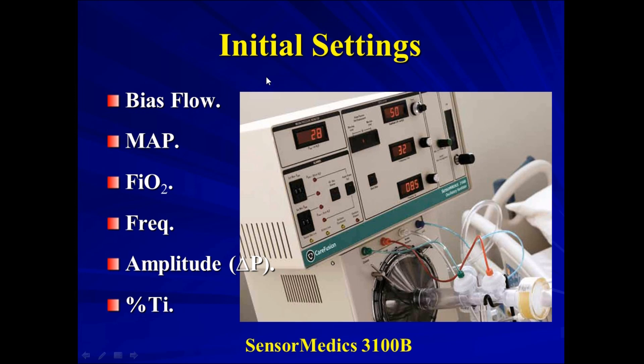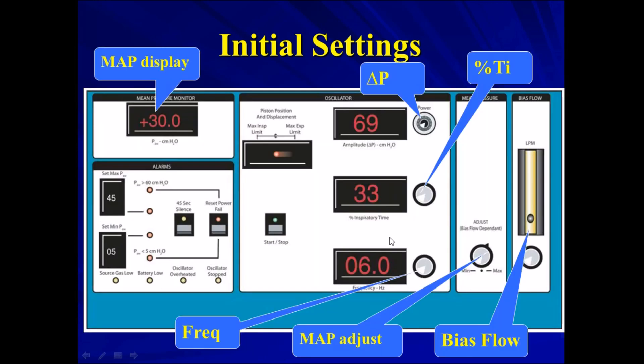To repeat the settings: the bias flow, the mean airway pressure, the FiO2, the frequency, the amplitude or delta pressure or power, and the percentage of the inspiratory time. We are talking about the SensorMedics 3100B. The mean airway pressure can be decided from this knob, along with the bias flow, the delta pressure or power, the inspiratory time, and the frequency.